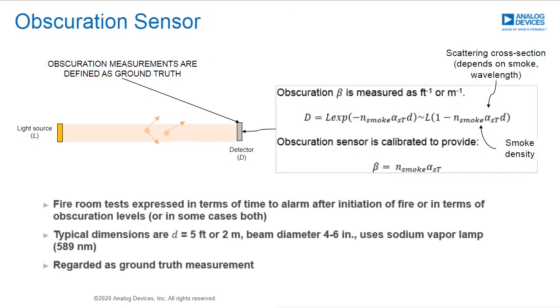Now, the golden standard of smoke detection measurements when you're talking about optical smoke is an obscuration sensor measurement. So when you take your smoke detector to, for example, the Underwriter Laboratory who created the UL 217 spec, what they have is a light source and a detector that's about 4 or 5 feet away, and they have some signal when there's no smoke present, and it's basically 100% signal. And as smoke enters this beam, it starts to obscure the beam so that the signal being detected starts to reduce.